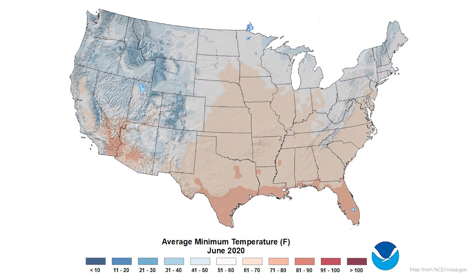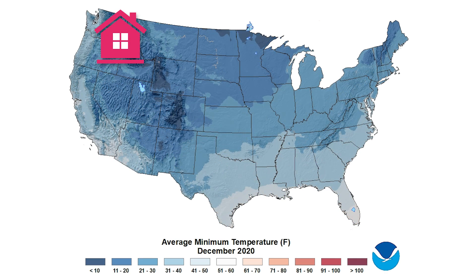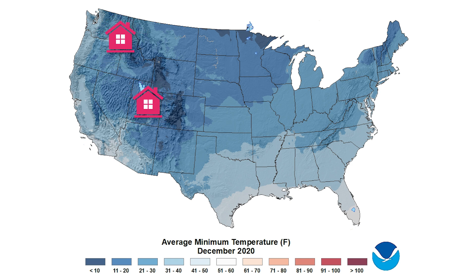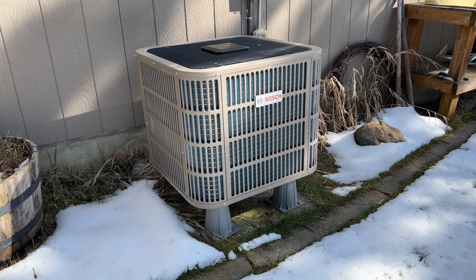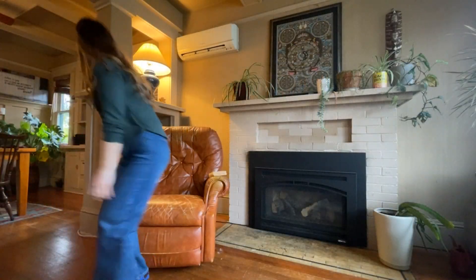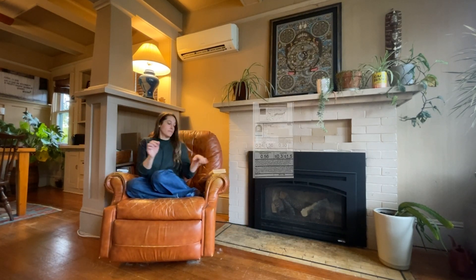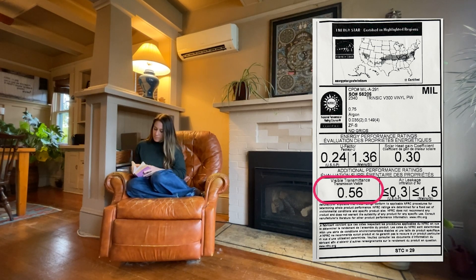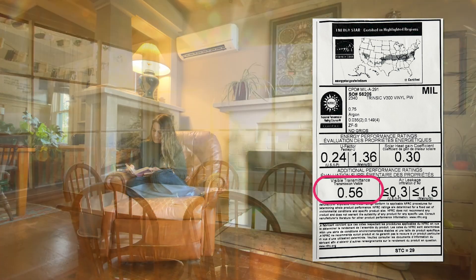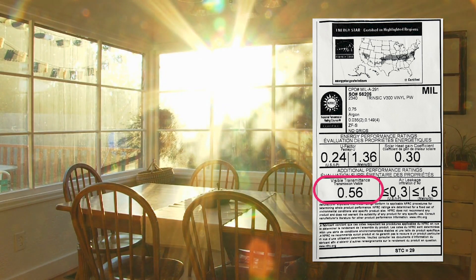Different regions have different requirements for solar heat gain. A house in the north without southern-facing windows may benefit from a higher SHGC rating, while a home in the south will most likely want to keep the sun out of the home through the year. In a home that has air conditioning, having a lower SHGC can have a major impact on energy use, because solar heat gain can be the reason for as much as 50% of the cooling load needed in the home. The NFRC label also includes a visible transmittance rating using a 0 to 1 scale to indicate the amount of visible light that can pass through the glazing. A larger number indicates more visible light can pass through the window glazing. This is directly related to the rating of the SHGC.